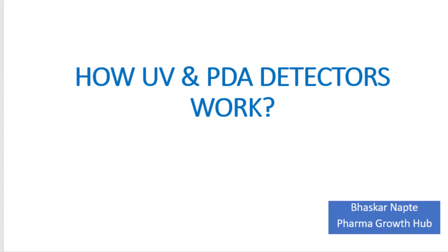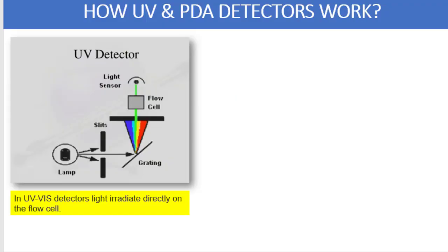Let us first begin with the discussion on the UV detector working principles. You can see in the diagram that there is a lamp, slit, diffraction grating, another slit, then there is a flow cell followed by the light sensor. This is the overall construction or the components of the UV detector.